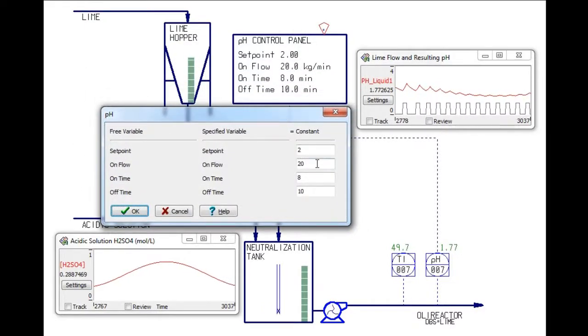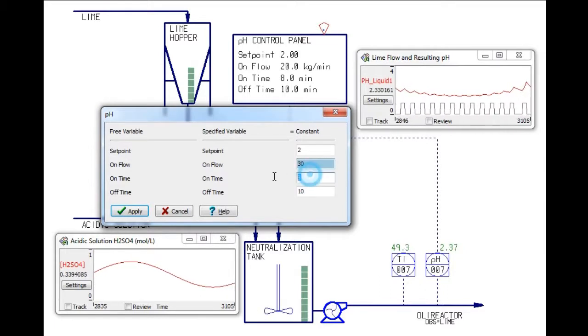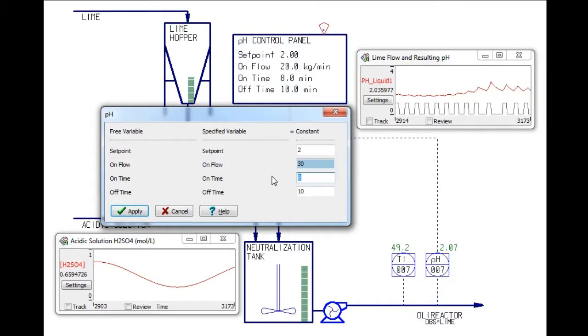First, I will increase the amount of lime fed from 20 to 30 kg per minute. I've done this because at times when the incoming acid concentration is high, the controller has trouble keeping up.